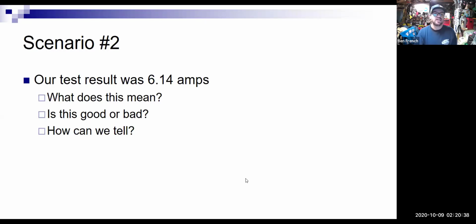So different scenario now - scenario 2 is that you're reading 6 amps. Now remember, 6 amps really isn't enough to make the power window work. So what that means is that I am flowing some current, a substantial amount of current, however this is not enough to actually get the window to lift the motor, okay?